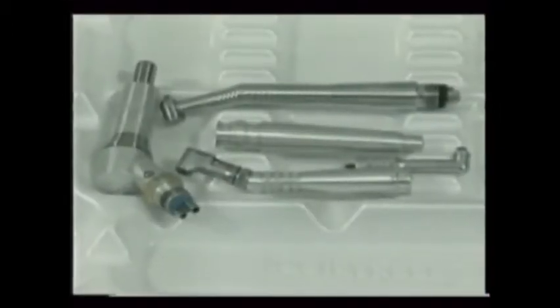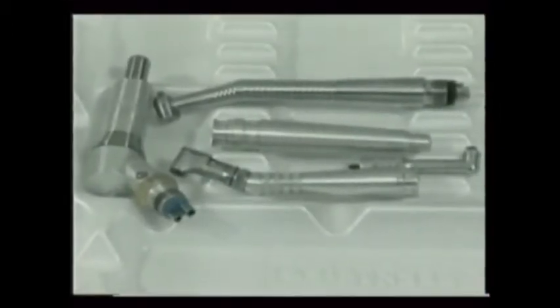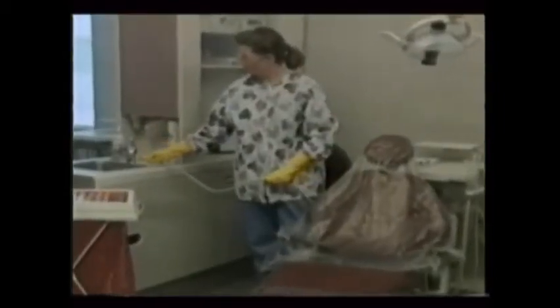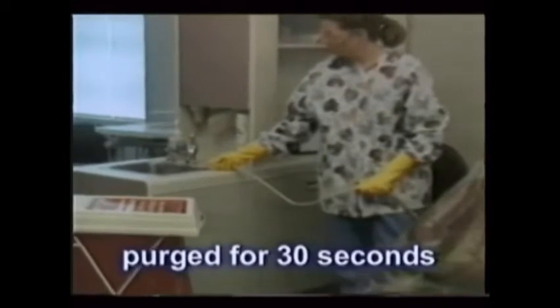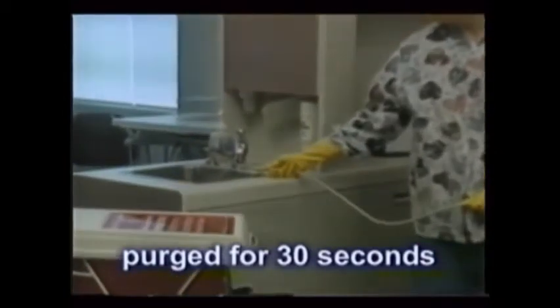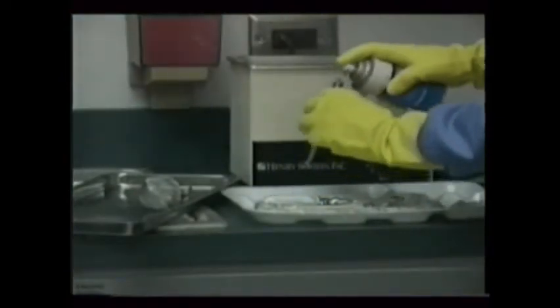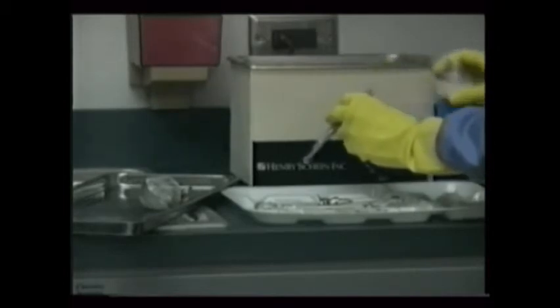Dental air-driven handpieces have special needs when being sterilized to protect them from damage. As you'll see, the high-speed handpiece should be purged with air and water for 30 seconds or so before leaving the treatment room. Next, with a spray can of lubricant used only for dirty handpieces, the handpiece is sprayed within, wiped clean, and then packaged for the autoclave.